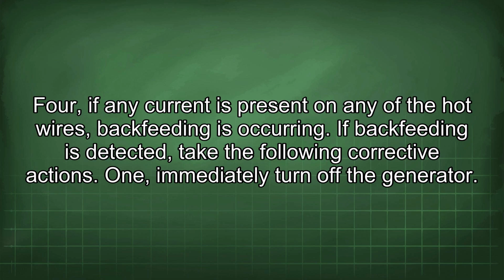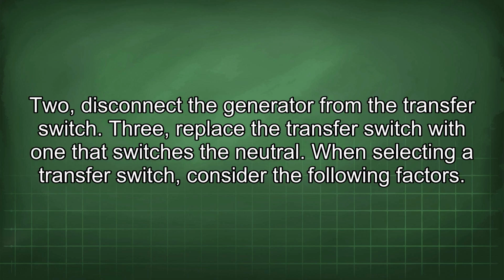If backfeeding is detected, take the following corrective actions. 1. Immediately turn off the generator. 2. Disconnect the generator from the transfer switch. 3. Replace the transfer switch with one that switches the neutral.